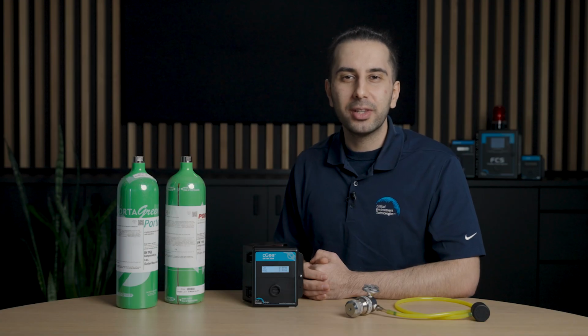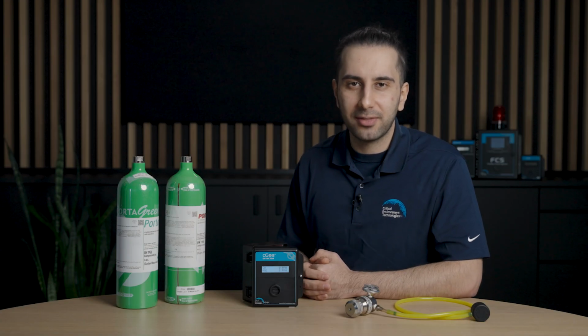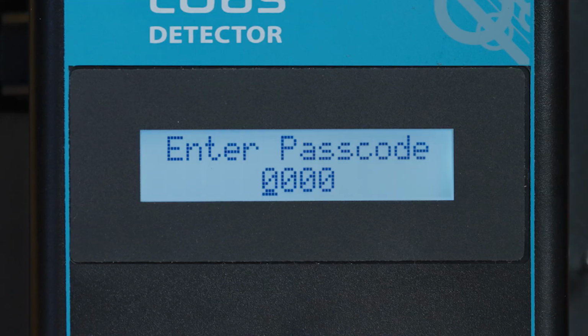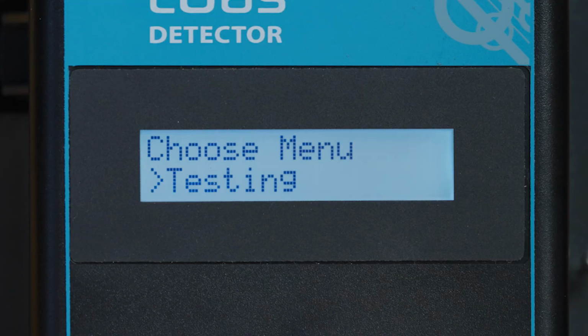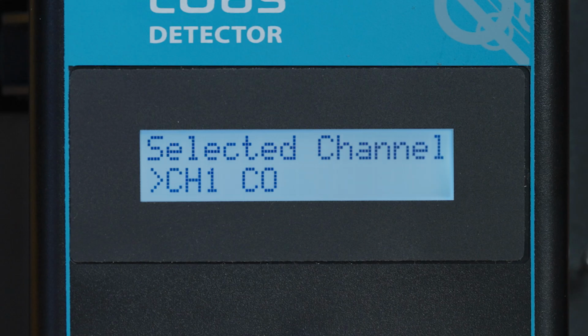To start, we will need to set the calibration gas value. Input passcode 2020 and press Enter. Navigate to Calibration, then select a channel, press Enter. This detector has two channels. First channel is for carbon monoxide and the second one for nitrogen dioxide.